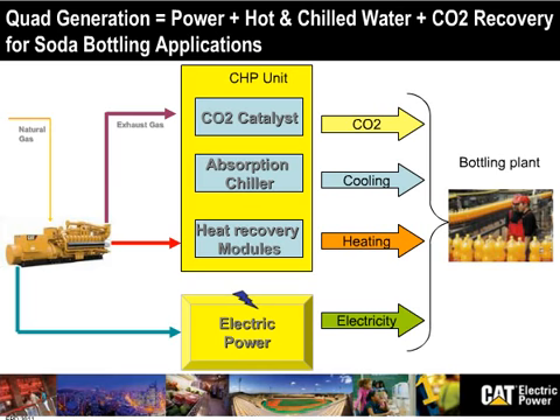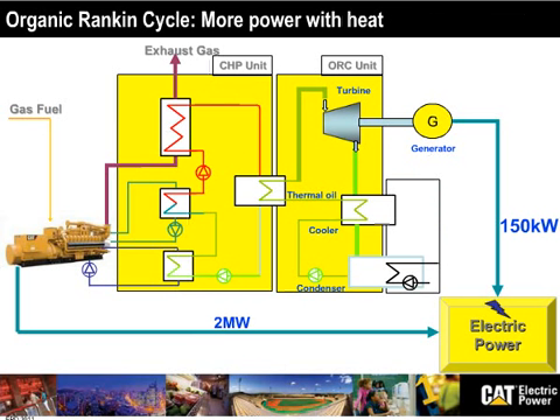If you don't want to use the heat from our CHP system, what else can you do? You can do more power. Most of you maybe are familiar with these combined cycles, and actually here it's almost a combined cycle. It's called an organic Rankine cycle. It's the way to use the heat that we recover from the CHP into a power generation system. In combined cycles, the media is usually water and steam. In ORCs, it is actually a different fluid. That's why we call it with a different name. It's a thermal oil that is very special and will produce extra power from the CHP.